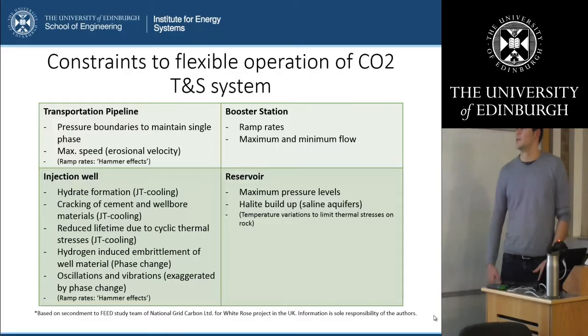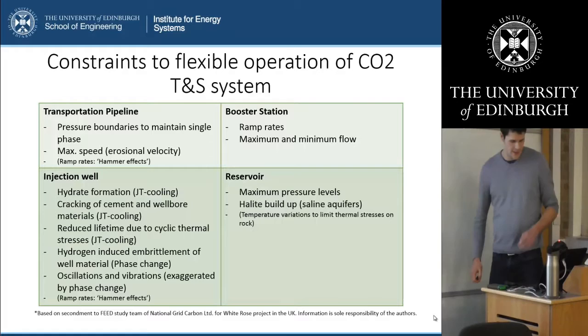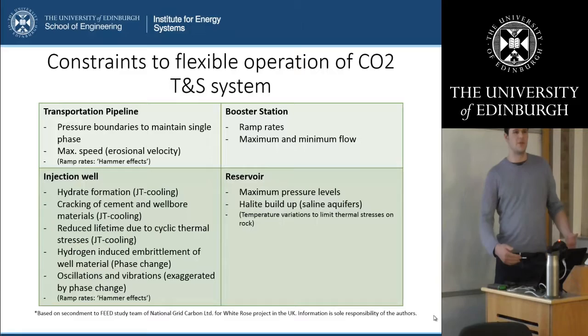As a next step I've looked at the constraints of flexible operation of the CO2 transportation storage systems, through an extensive literature review and talking to the CCS FEED study teams of the two CCS demonstration projects. For the transportation pipeline, booster station, and reservoir, most constraints have to do with staying within certain pressure limits or respecting certain flow limits. But for the injection well there are several other risks to consider when cycling regularly: the risk of hydrate formation, cracking of cement and wellbore materials, reduced lifetimes due to cyclic thermal stresses, hydrogen-induced embrittlement of well material, and oscillations and vibrations.